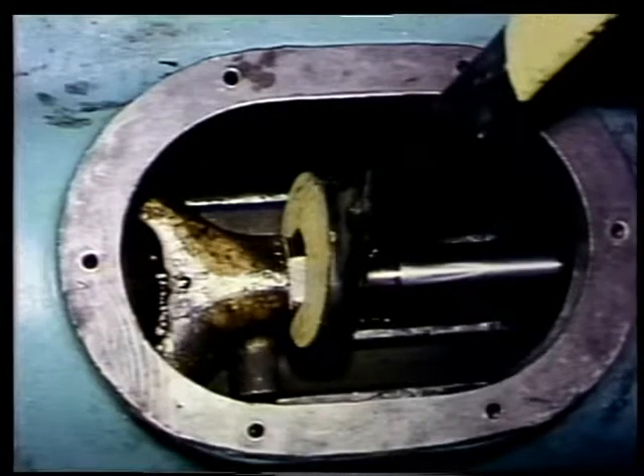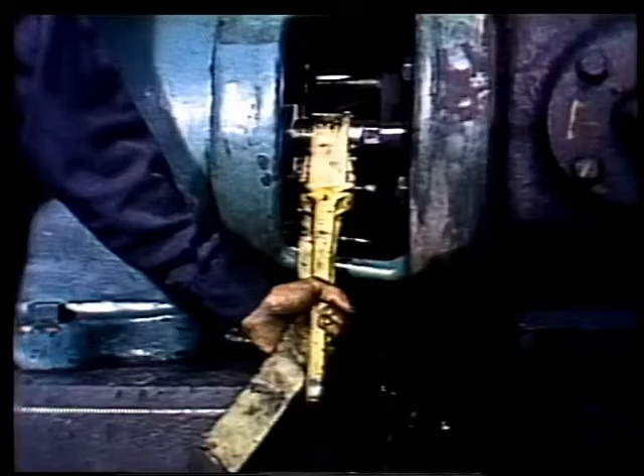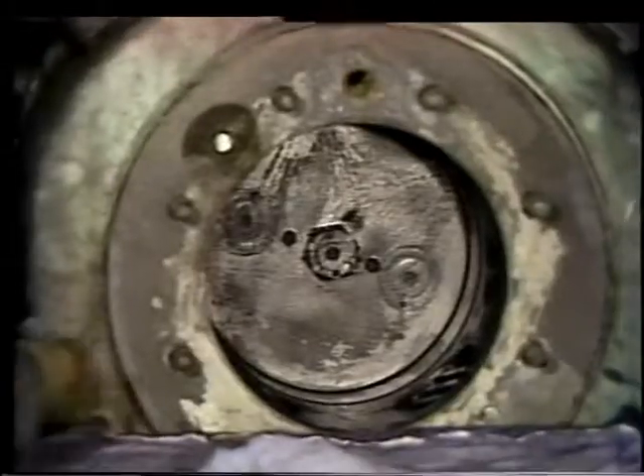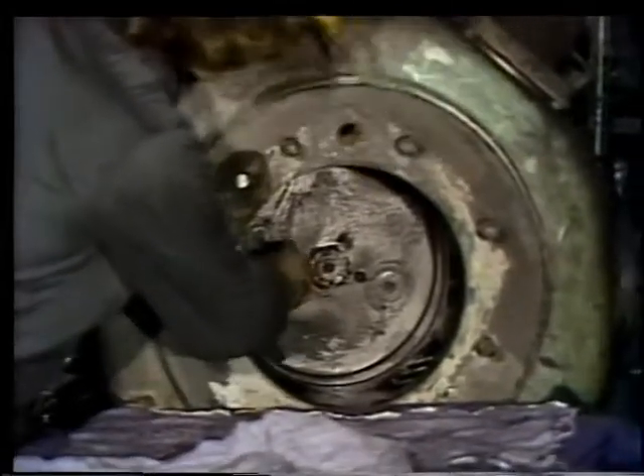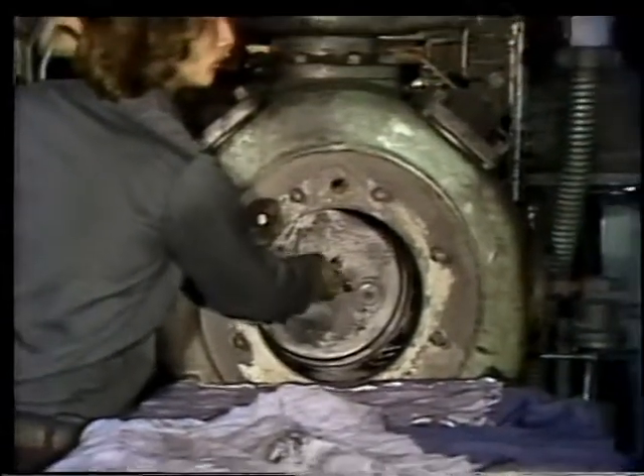Now you're ready to unscrew the piston rod from the crosshead. To do this, you attach a strap wrench to the piston rod. The strap wrench enables you to get a good hold on the piston rod and makes it easier to unscrew it from the crosshead. After the piston rod has been unscrewed, you remove the piston and piston rod from the cylinder.